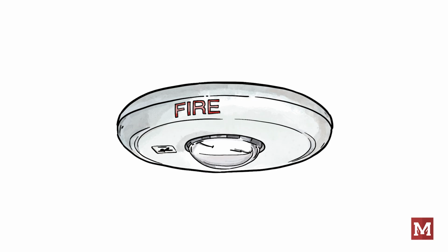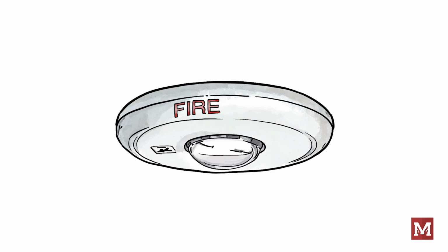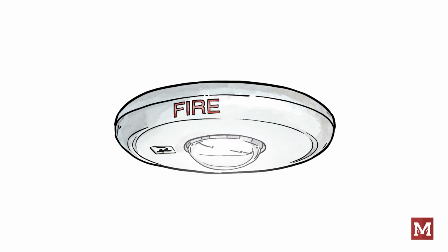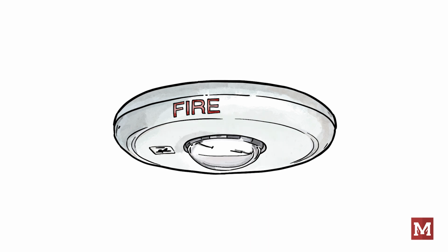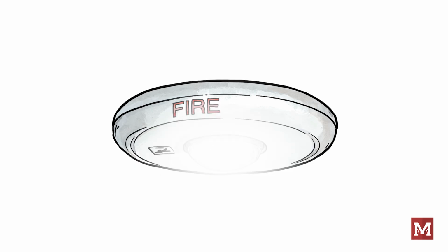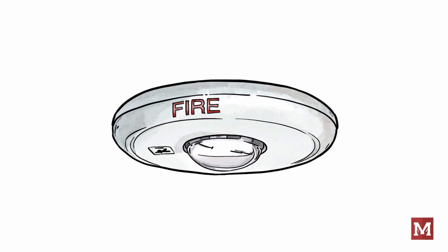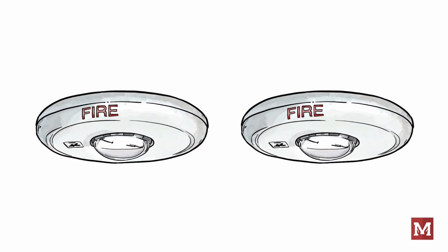Let's talk briefly on the term synchronization. There are a few rules regarding light coverage from strobes. I mentioned the amount of light that needs to cover a space, or a light intensity. Strobes also need to flash in a very specific frequency. The flashes must be no more than 2 flashes per second and not less than 1 flash per second. Any strobe that flashes must simultaneously flash with other strobes that are within the same field of view. So the common term here that we use is synchronized.